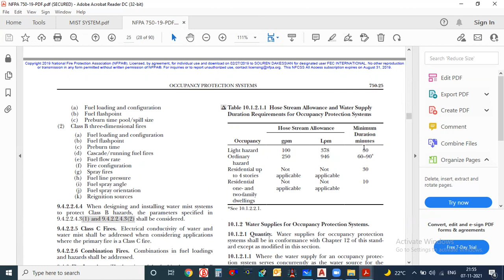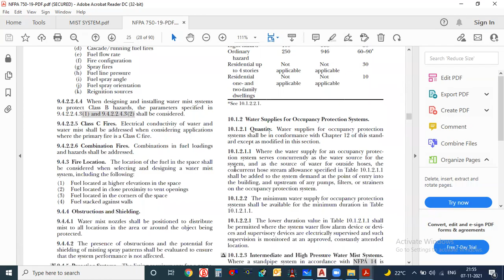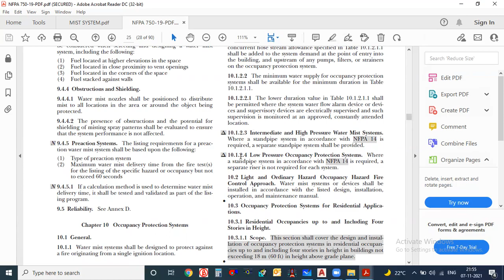Now what is this hose stream allowance? This hose stream allowance is nothing but, if we are using the hose system, then we have to follow this. But here they have not given anything about inside or outside hose, just the hose stream allowance. So whenever we are using the hydrant system, we have to follow this particular GPM, 100 GPM and 250 GPM. And duration is also given here, 30 minutes or 60 minutes. That means for 30 minutes, whatever tank we are selecting should at least supply water for up to 30 minutes. Our understanding from this duration is this only. Like for light hazard, you have to design a tank in such a way that it supplies water for at least 30 minutes. And apart from that, here they have given just follow NFPA 14. Whenever you are having a standpipe system, follow NFPA 14.